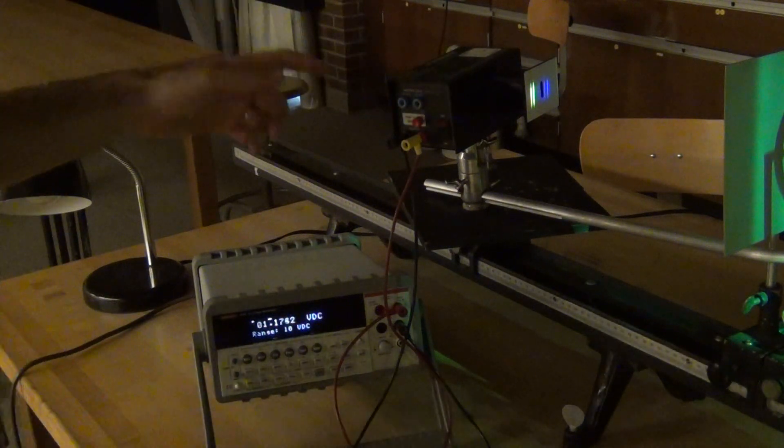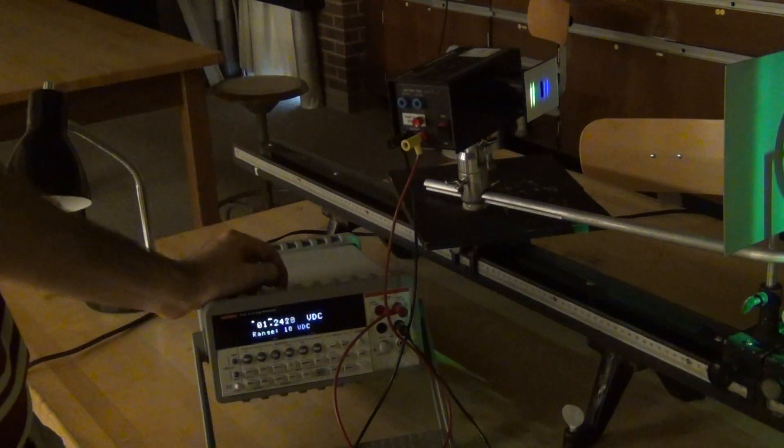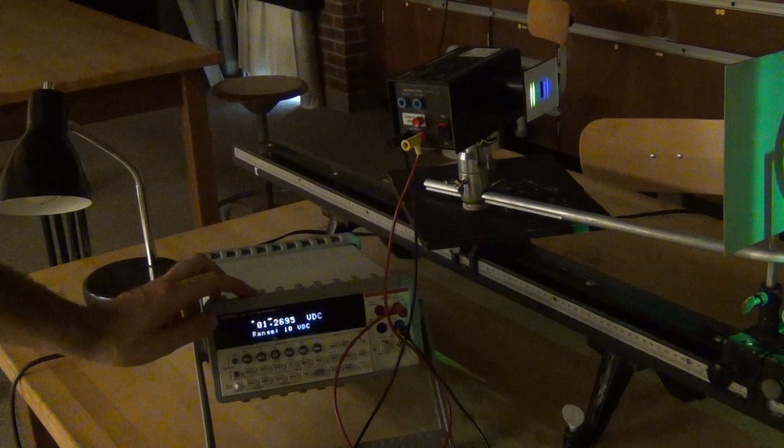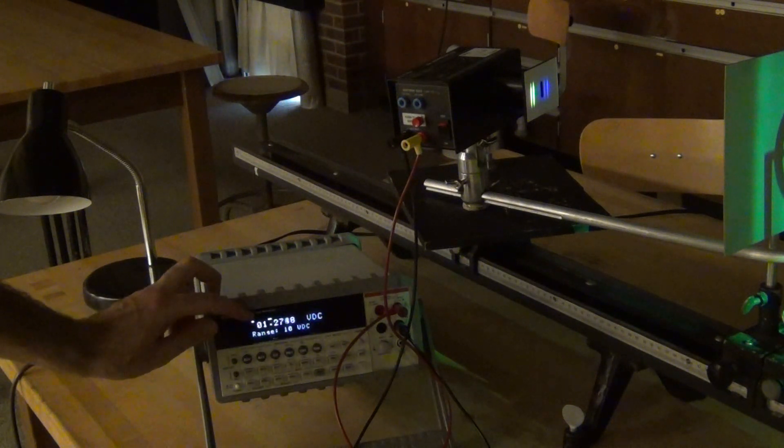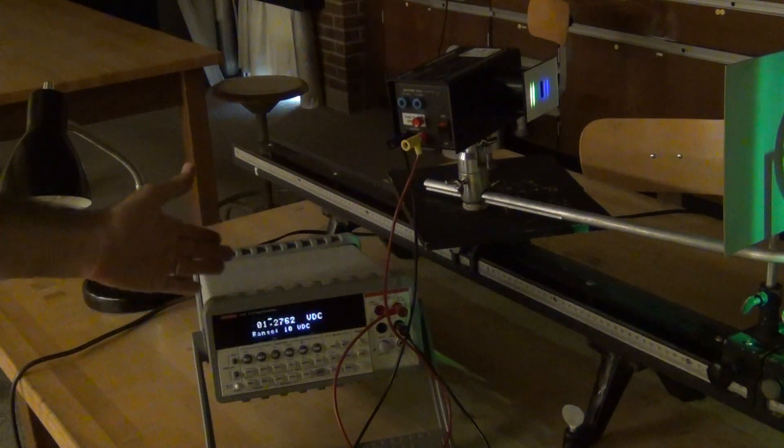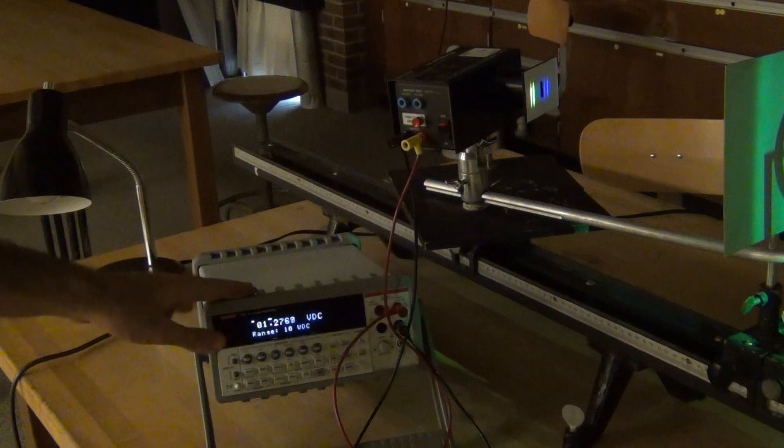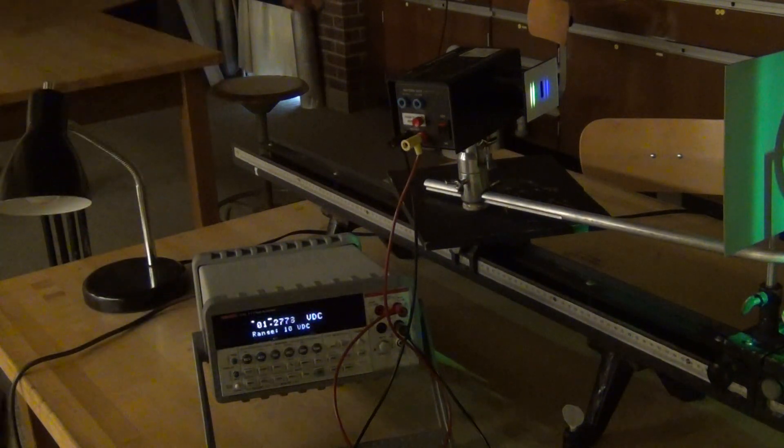Press the zero measurement that discharges the capacitor, and when you release that, the capacitor will start to charge. The charge will slowly build up and might take up to three minutes to stabilize. You should note the voltage every 30 seconds until it is stabilized, and then record that voltage for that wavelength.